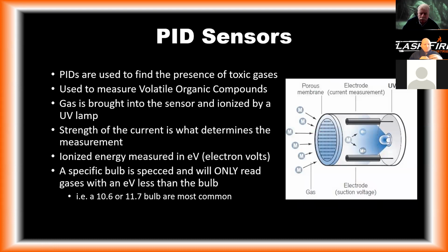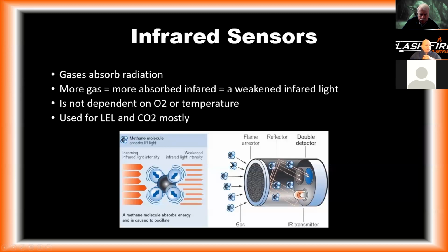I'll give you some better examples of this later, but basically you buy a specific bulb and it will only read gases with an electron volt or ionization potential less than that number. So you guys have a 10.6 bulb. So when you guys are looking up gases in the NIOSH guide, if it has less than 10.6, then that's going to be a gas that you guys can read on the PID meter.